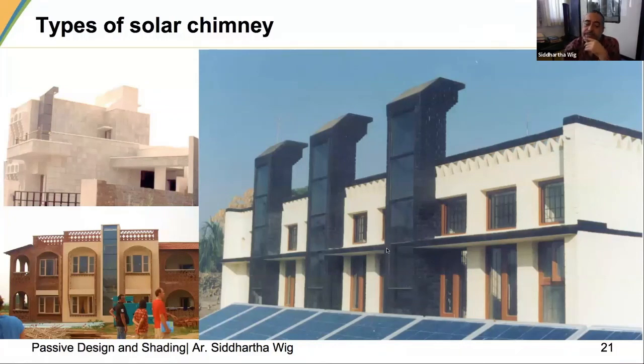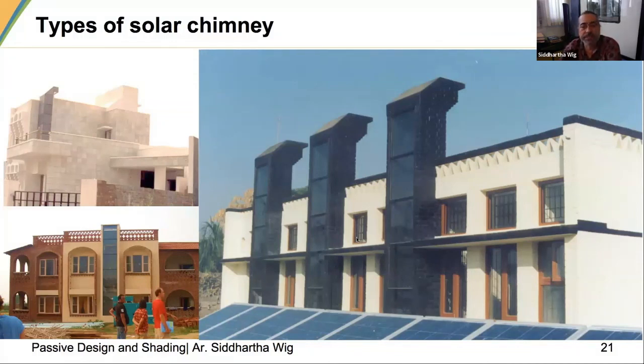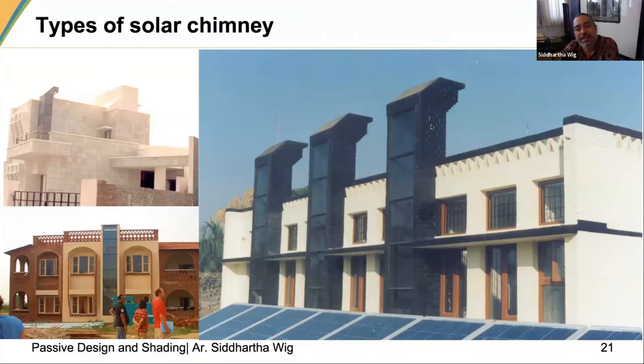The image on the right shows a 200-kilowatt solar power plant control room building we did for PEDA. Three chimneys were evacuating all the hot air from the equipment rooms inside. This was a more conventional solar chimney facing south — it had glazing, black internal metal-cased walls, and the outside was also black. Air came out at a little height above the slab.